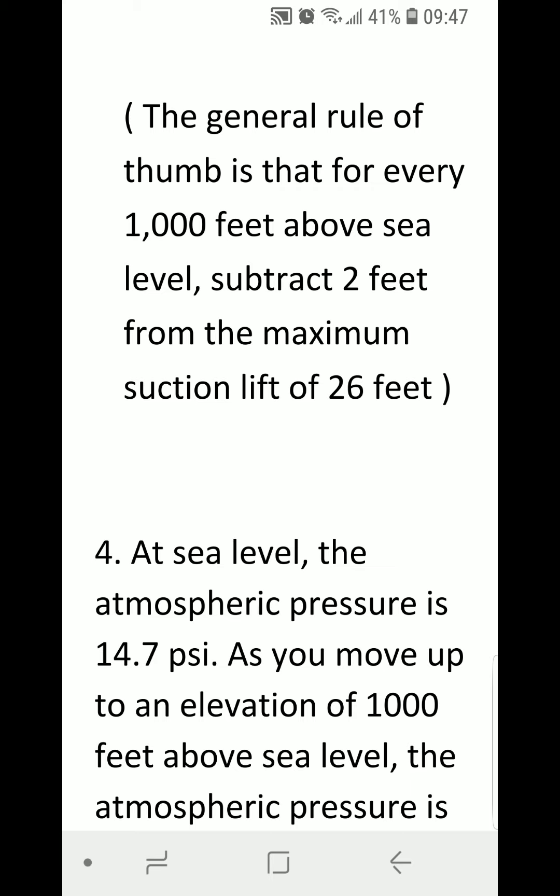For every 1,000 feet above sea level, we need to subtract 2 feet from the maximum suction lift of 26 feet.